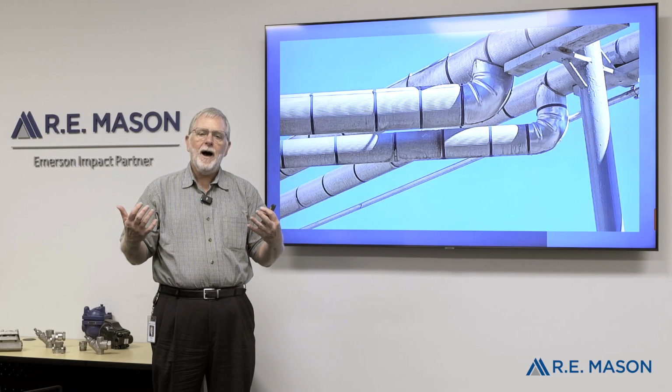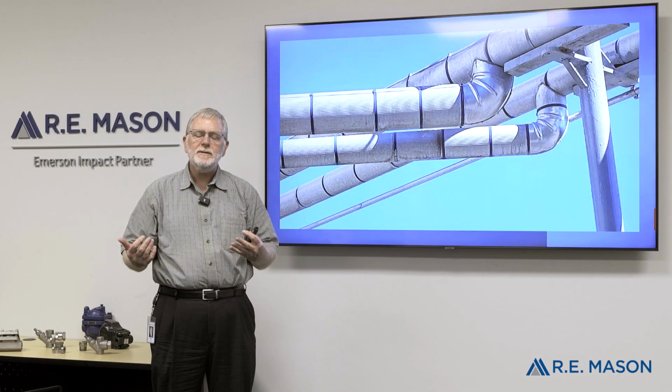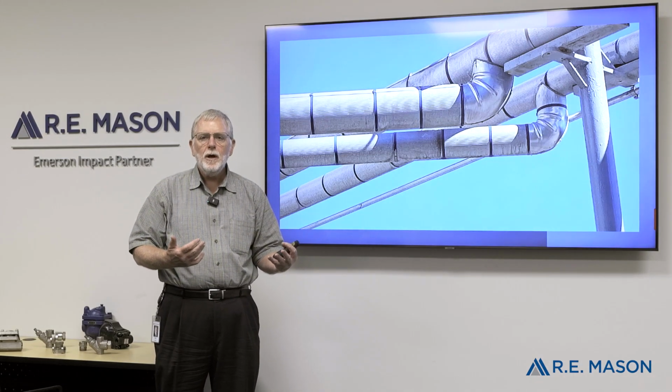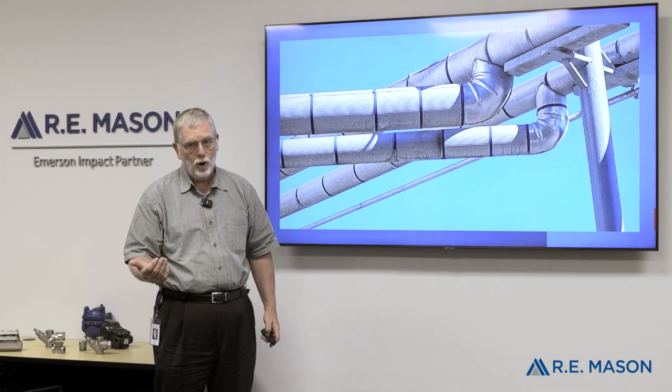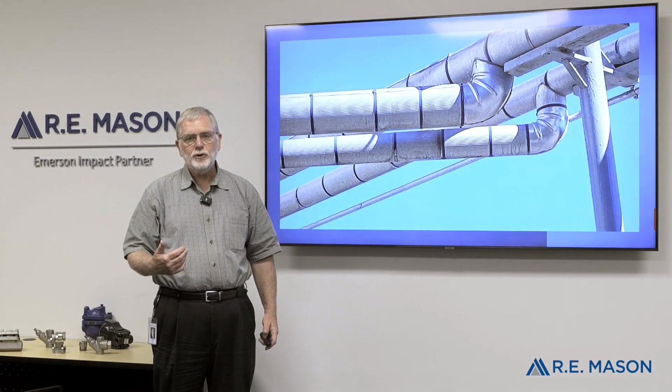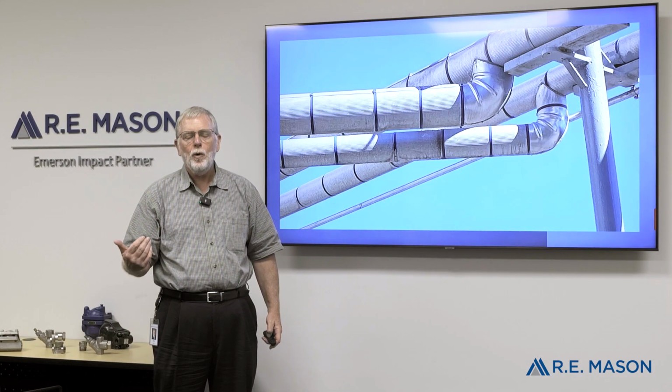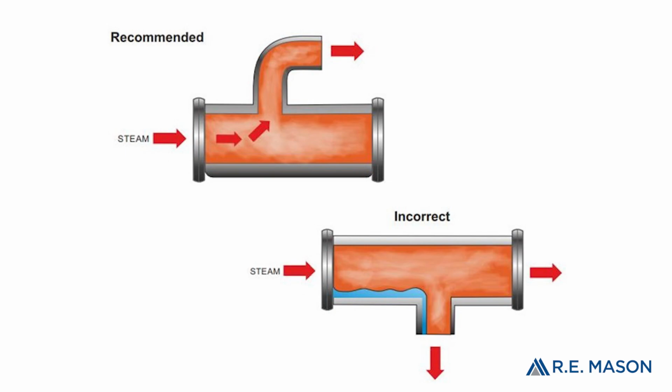Putting it back in on the bottom like that, with the pressure, you increase back pressure in your system, which, depending on how things are installed, could make your trap work or not work. And this can cause problems as well. If the trap's not working, why is it not working? And here's just an example of where we take the steam off the top, not off the bottom. If it's off the bottom, it's what we call a drip leg.